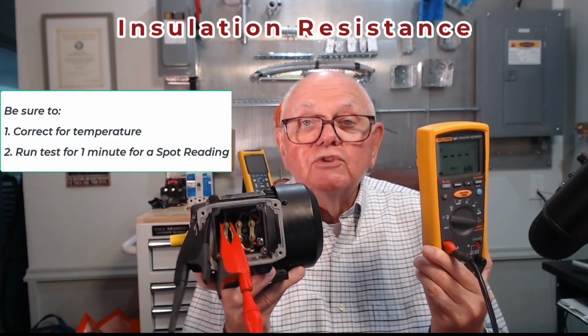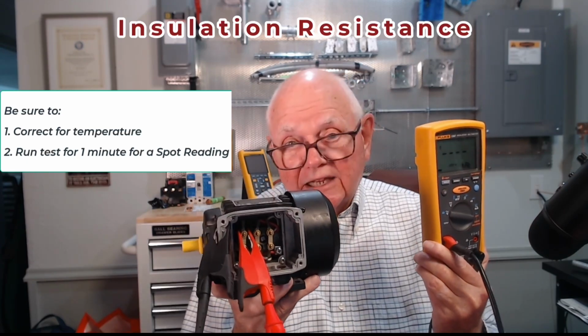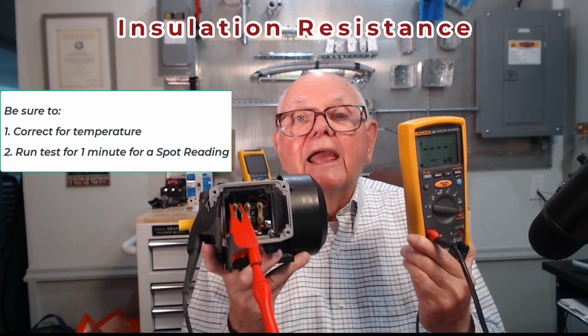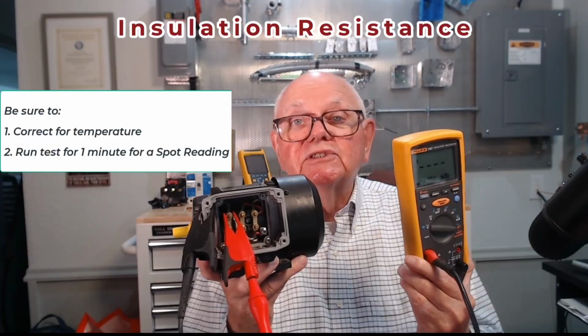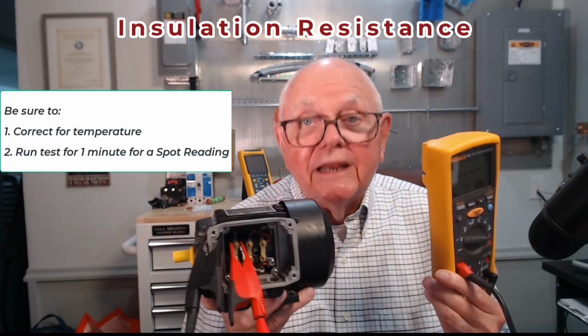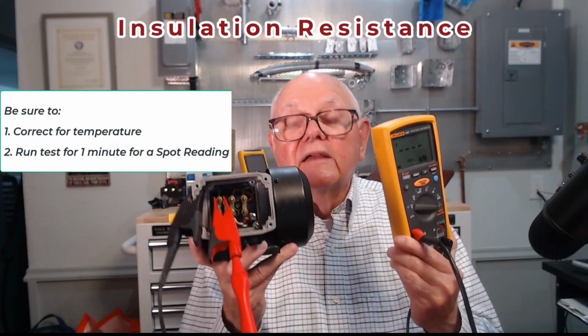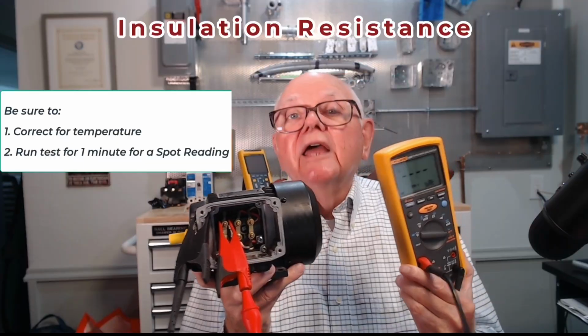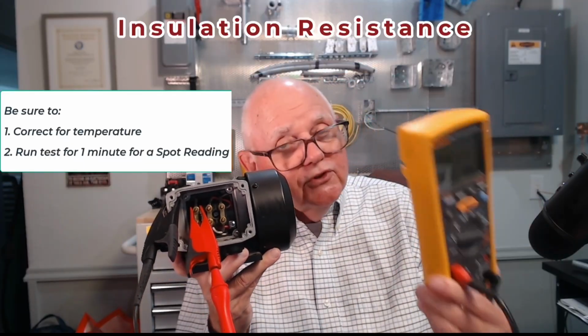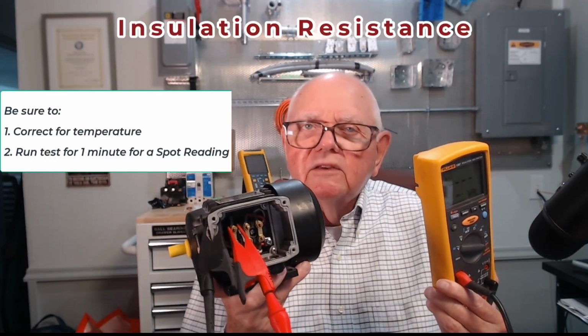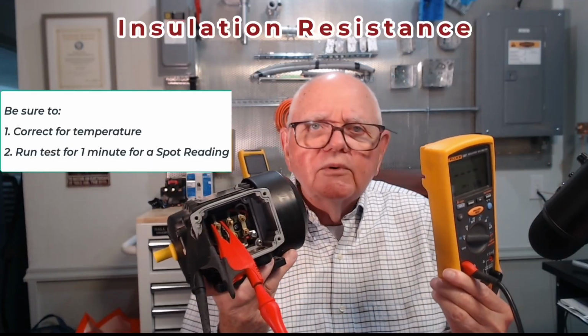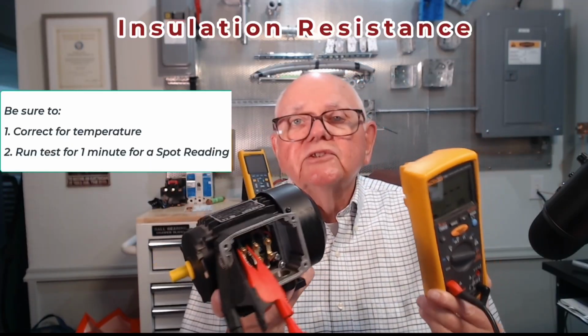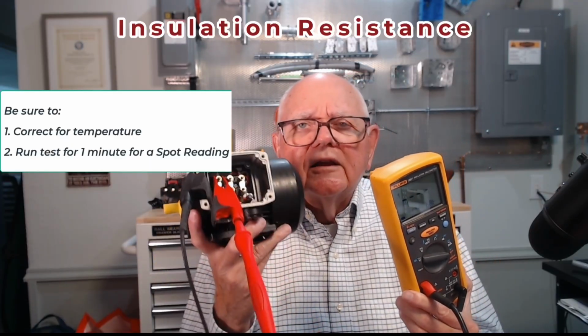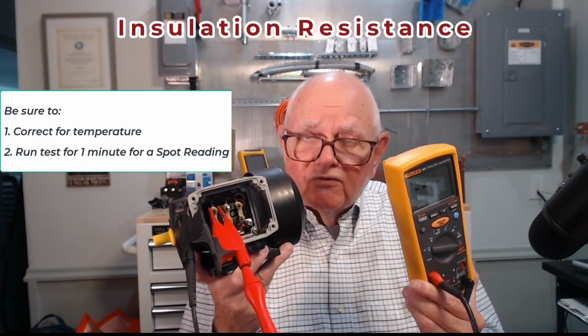So what we're going to do is a spot reading test. We're going to let our insulation resistance tester run for 1 minute and take a reading. That's our spot reading test. And if I do it that way today and you do it that way next month when you do the maintenance on this motor, or in 6 months, whatever, we'll be consistent. So correct for temperature and make sure that you do your readings properly.